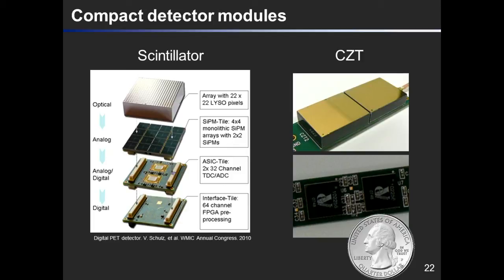Each detector contains 6 by 8 pixels. Each pixel is 2.5 millimeters by 2.5 millimeters square. If you flip this printed circuit board, you will see the two ASICs we used. Each ASIC reads out one detector. Compared to the CdTe-based detector module, I have one photo showing a scintillator-based detector module. This is one scintillator coupled to a silicon PM-based light sensing device. Then there is a readout ASIC for analog signal processing, then there's a digital part. I want to say this is the most compact scintillator-based detector as of today, made by Philips. If we use the same size and thickness for the detectors, the total size of this one is about 20 to 30 millimeter, and our detector module is 7.5 millimeter thick.